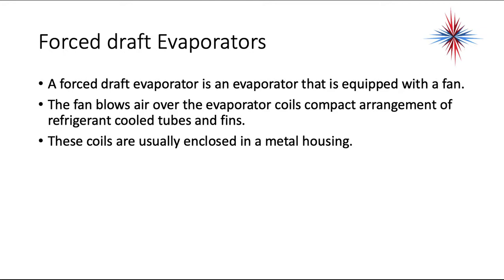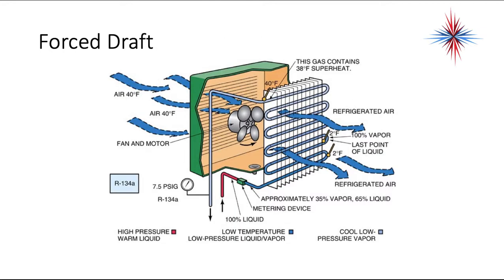Force draft evaporators is what we really want to concentrate on. A force draft evaporator is equipped with some sort of fan to blow the air over the evaporator coils. It's a compact arrangement of refrigerant-cooled tubes and fins, and these coils are usually enclosed in a metal housing. In split systems, this will be on the air handler or furnace. In window units, you'll have it on the inside portion of the window unit. The fan blows air through the evaporator coil.